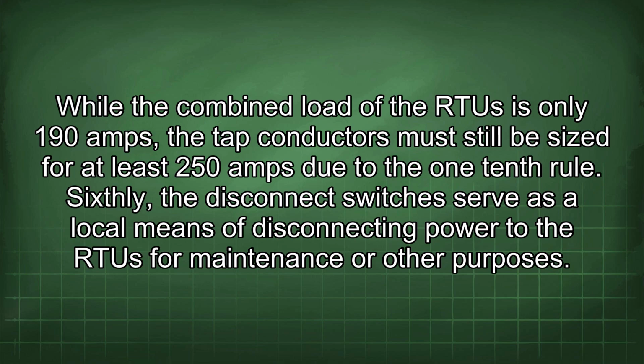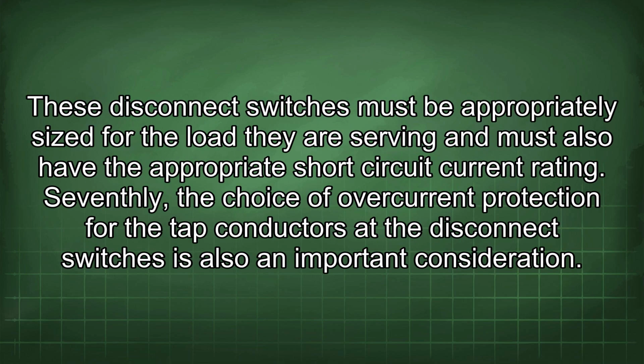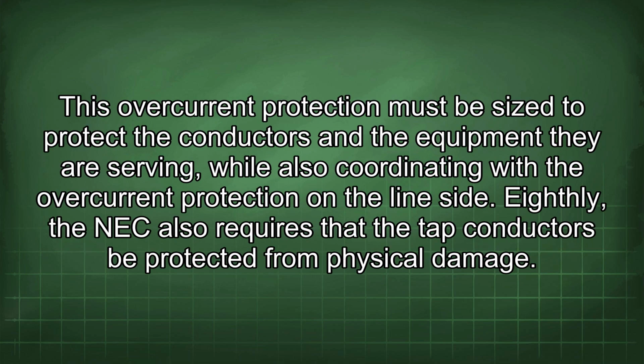Sixthly, the disconnect switches serve as a local means of disconnecting power to the RTUs for maintenance or other purposes. These disconnect switches must be appropriately sized for the load they are serving and must also have the appropriate short-circuit current rating. Seventhly, the choice of overcurrent protection for the tap conductors at the disconnect switches is also an important consideration. This overcurrent protection must be sized to protect the conductors and the equipment they are serving, while also coordinating with the overcurrent protection on the line side.